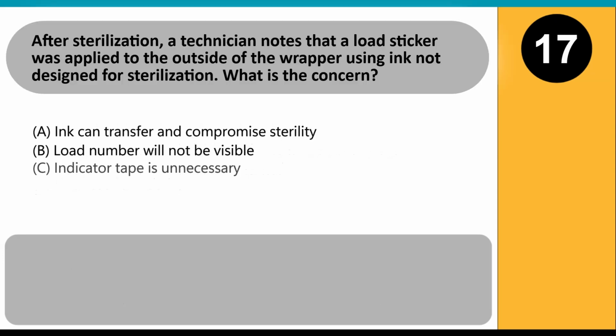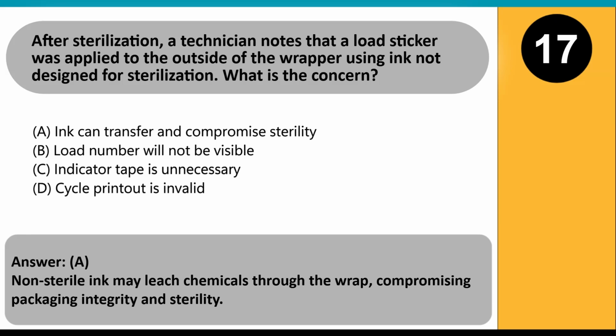After sterilization, a technician notes that a load sticker was applied to the outside of the wrapper using ink not designed for sterilization. What is the concern? A. Ink can transfer and compromise sterility. B. Load number will not be visible. C. Indicator tape is unnecessary. D. Cycle printout is invalid. Answer: A. Non-sterile ink may leach chemicals through the wrap, compromising packaging integrity and sterility.